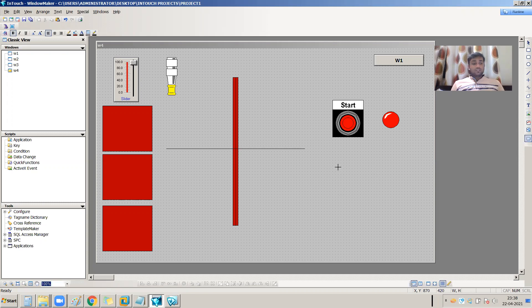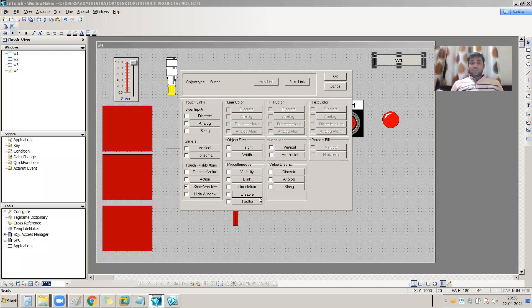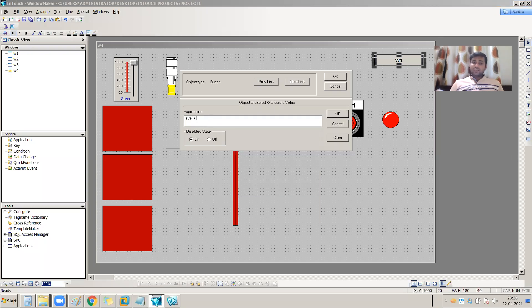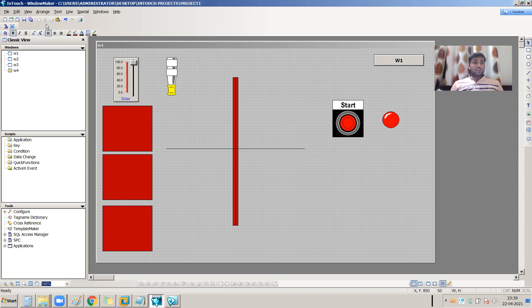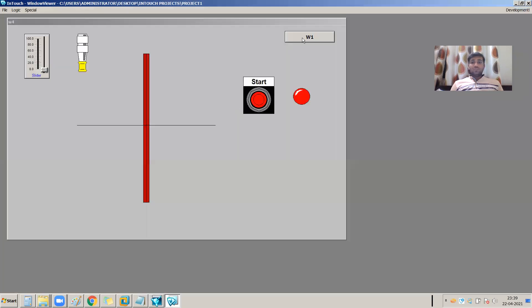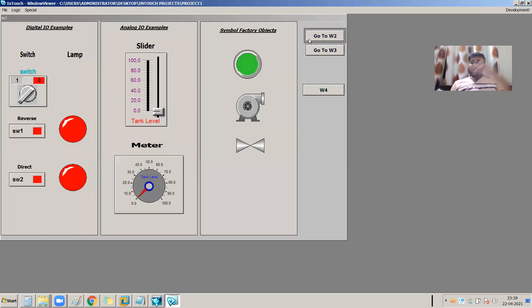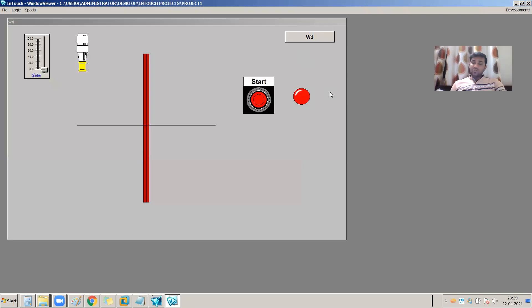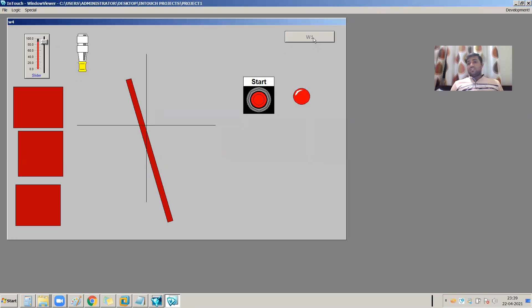Here is another example with a navigation button. I am setting the disable property so that whenever my level is greater than 70, this button should be disabled. Saving the screen and going to runtime mode. See - my button is working right now. If I press W1 I go to the W1 screen; if I press W4 I go to the W4 screen. But whenever my level is greater than 70, this button is disabled - I am pressing it but I am not moving to the W1 screen, because my level value is greater than 70. This is the disable property.